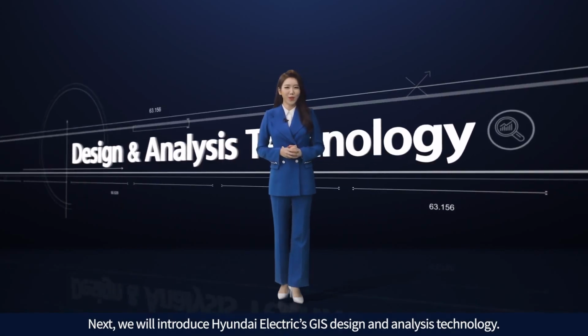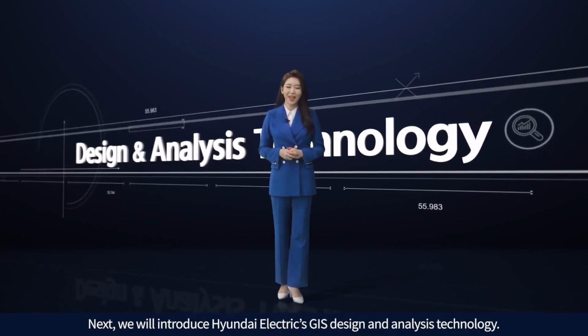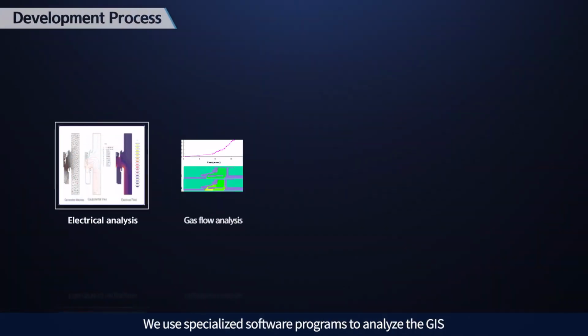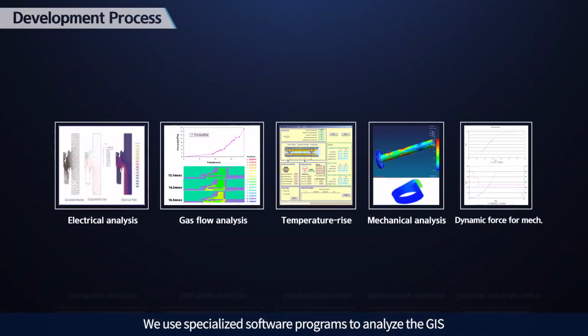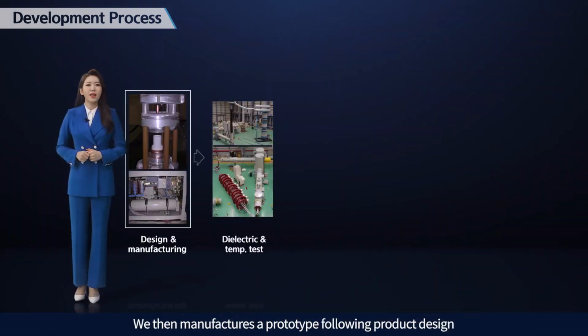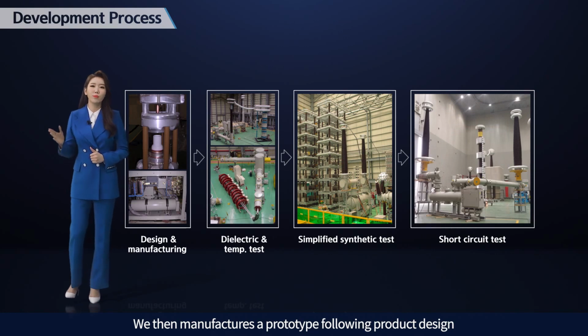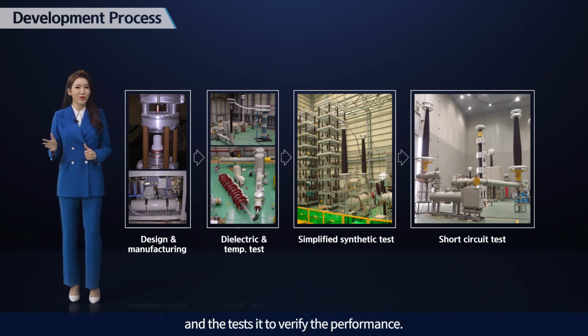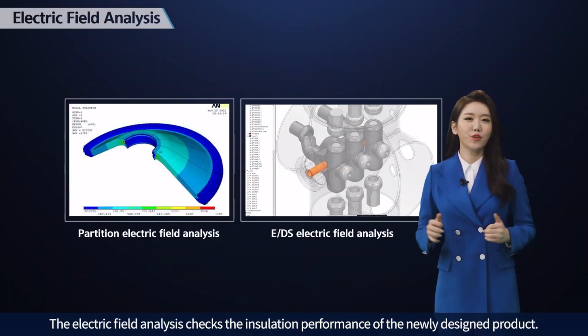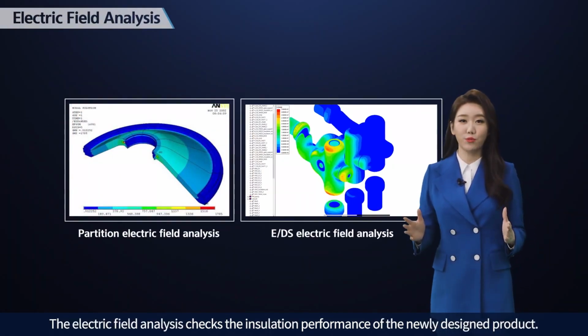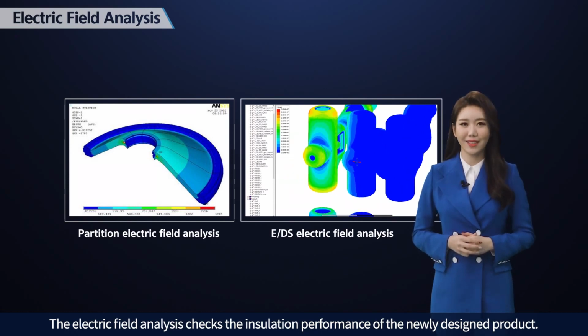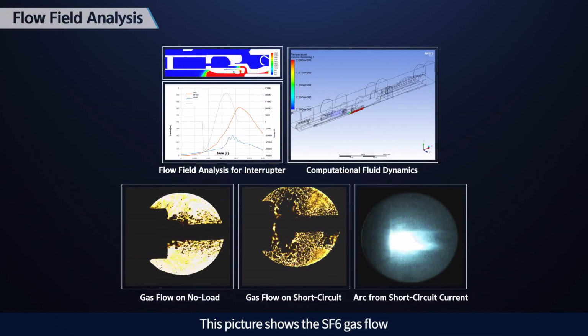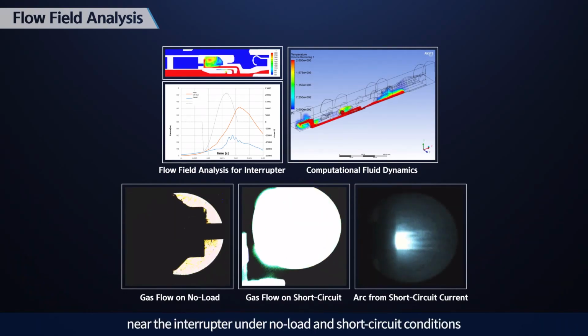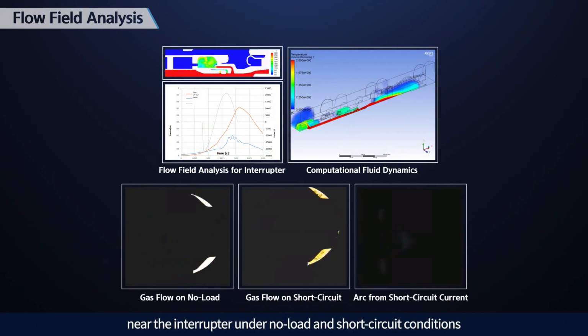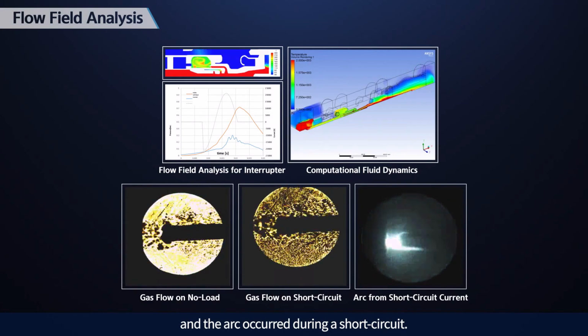Next, we will introduce Hyundai Electric's GIS design and analysis technology. We use specialized software programs to analyze the GIS and design the products based on the data. We then manufacture a prototype following product design and test it to verify the performance. The electric field analysis checks the insulation performance of the newly designed product. This picture shows the SF6 gas flow near the interrupter under no load and short circuit conditions, and the arc occurred during a short circuit.